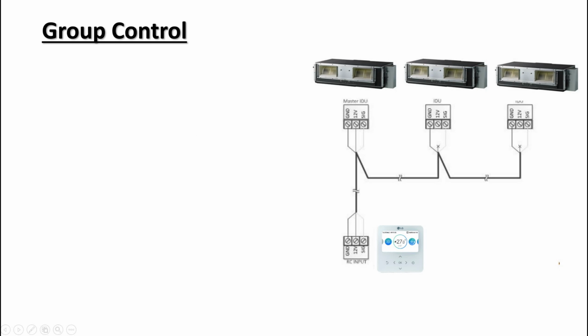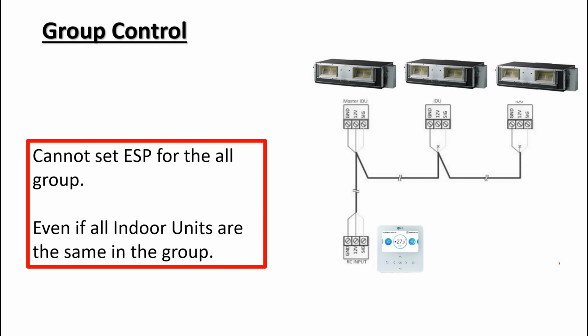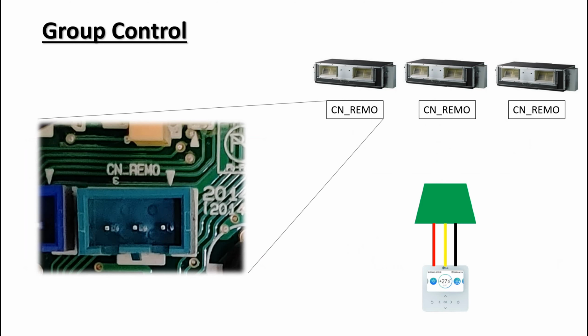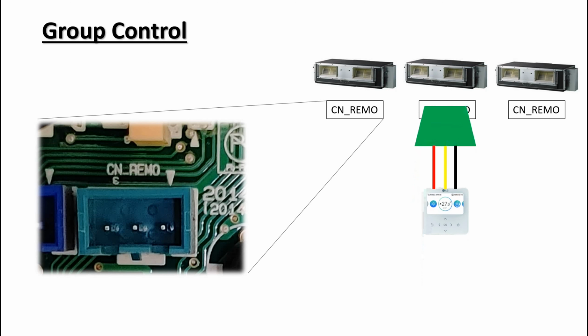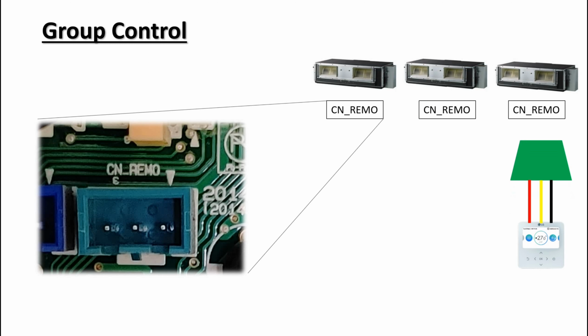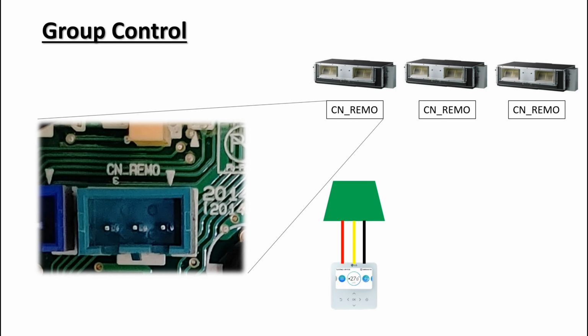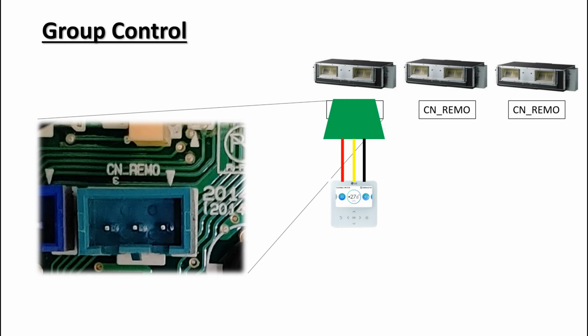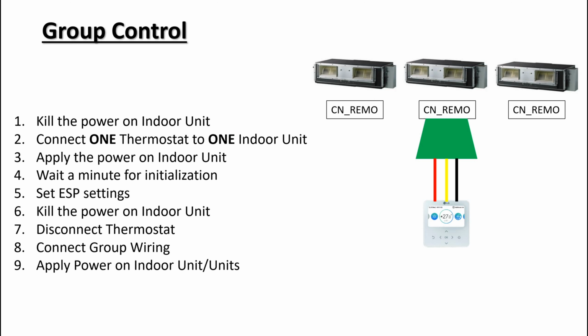A few words about group control. You cannot set up ESP for all units in a group from one thermostat at the same time, even if all units are the same in a group. You need to set ESP on all units in a group one by one. Get one thermostat, plug it into CN Remo plug on the indoor unit PCB, set up ESP, then reconnect to another unit and do the same. You need to do it once during the installation and setup process.